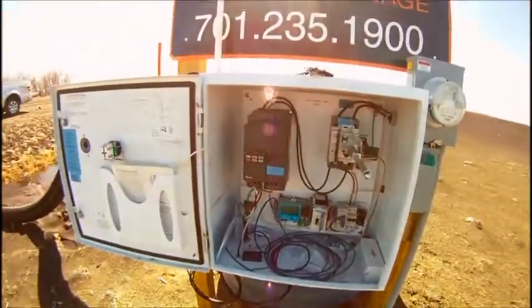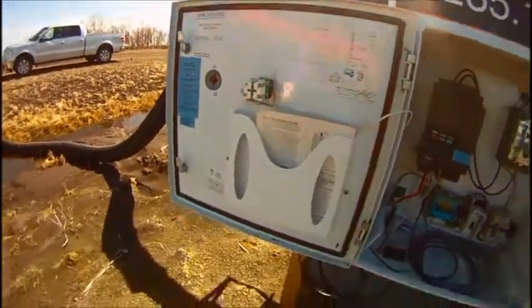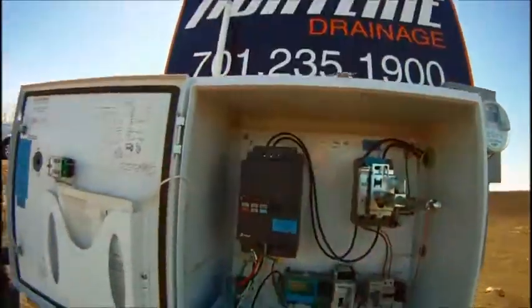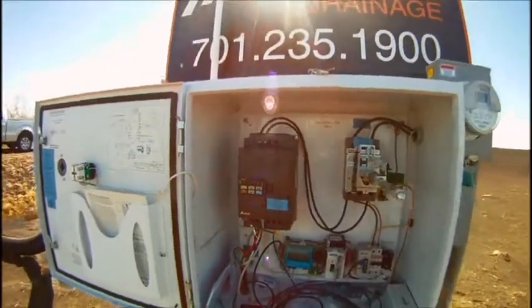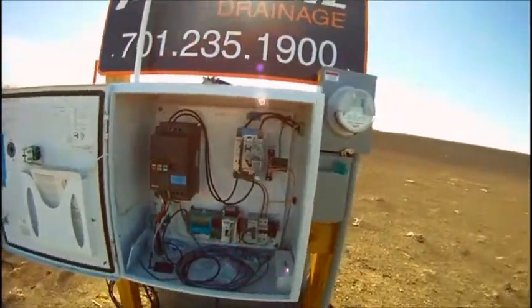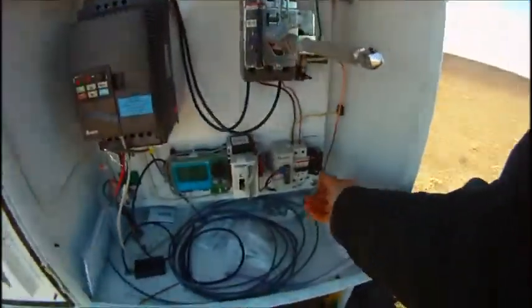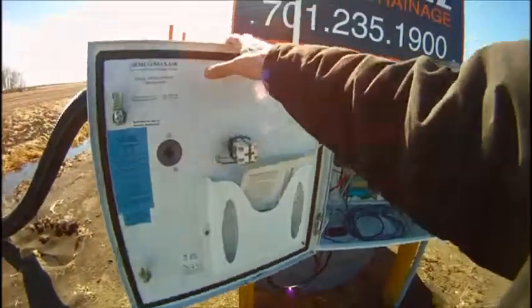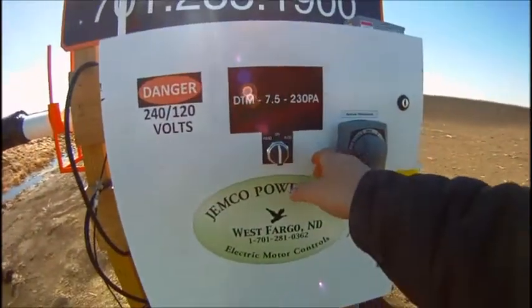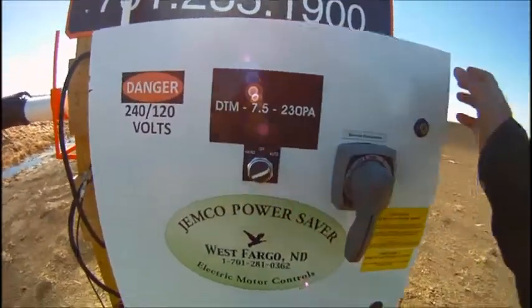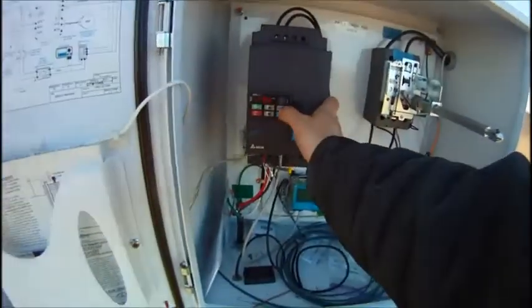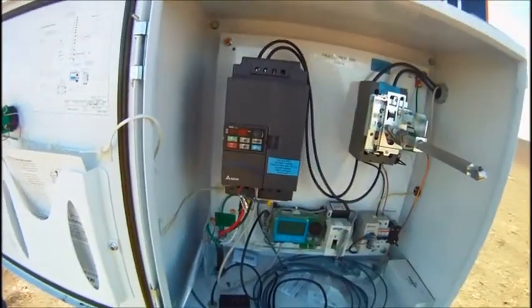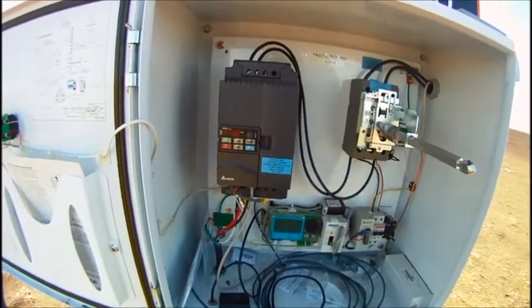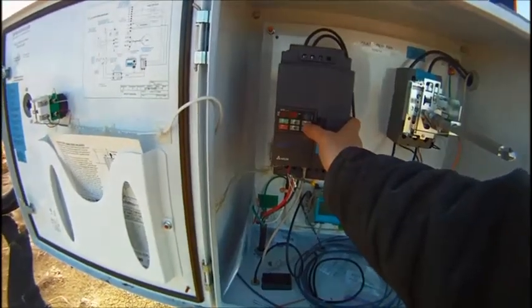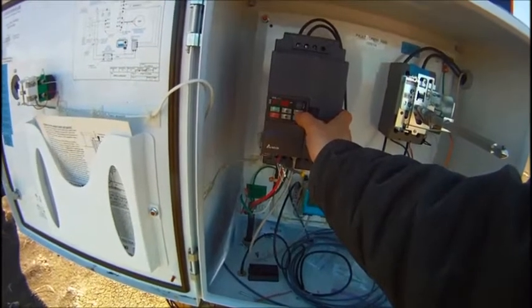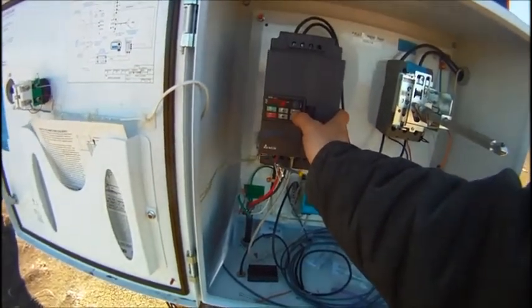Everything else looks in good condition. Doesn't look like any condensate or anything else has gotten inside of our system at all. And that's all you got to do for preseason. After that, make sure your bypass is back into the off and set your system back into auto. Make sure that your F is back to 3 again, which it is. Your H is 0. And it's not running right now. 0, 0, 0.